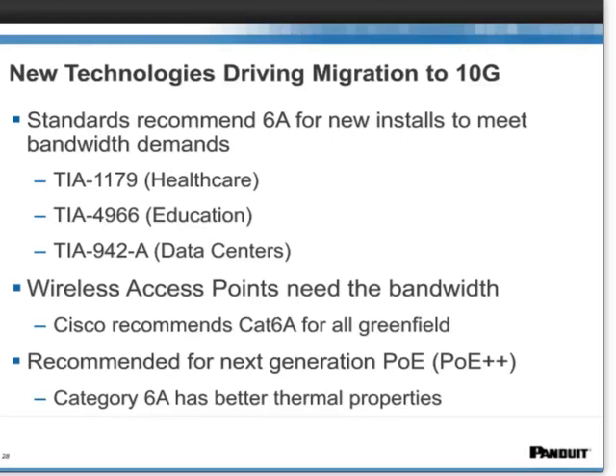All of the new technologies that we're experiencing now are really driving migration to 10 gig. The TIA standards recommend Cat 6A for new installations to make sure we meet bandwidth demands. This includes the TIA 1179 standard for healthcare, their standard for education, as well as the data center standard. Those new wireless access points need the bandwidth of 10 gig cable. While we did discuss options for NBASE-T, which gives you 2.5 and 5 gigs over 1 gig cable, Cisco as well as Panduit recommend Cat 6A for all Greenfield installations. And again, Category 6A is recommended for the next generation PoE or PoE++ because of those better thermal properties. It's more efficient cable to use when you have higher power going over your data cable.